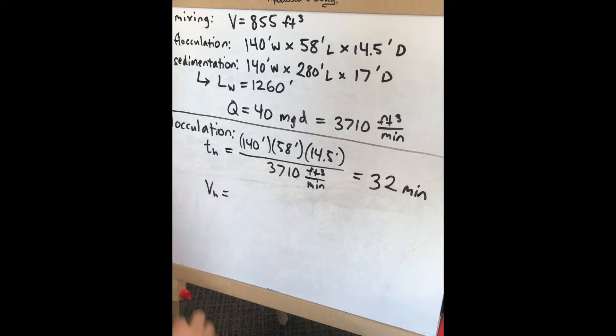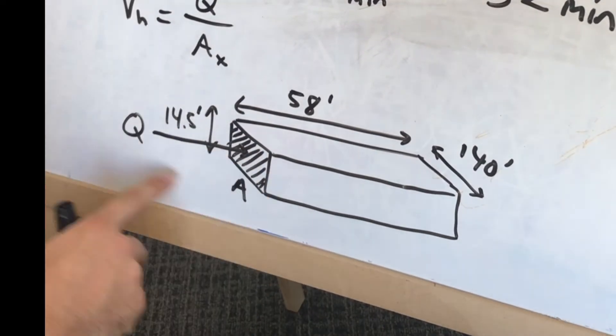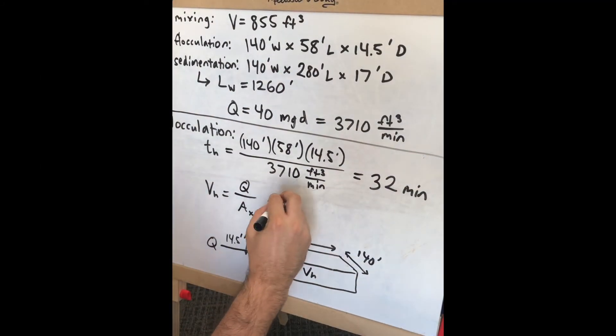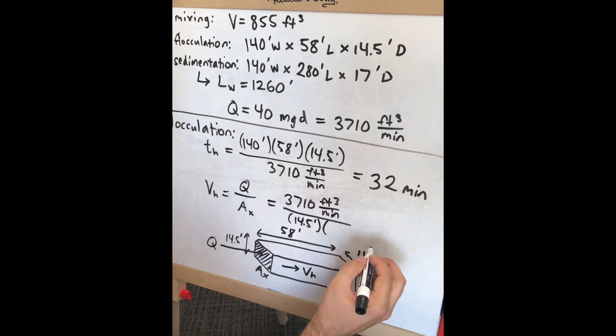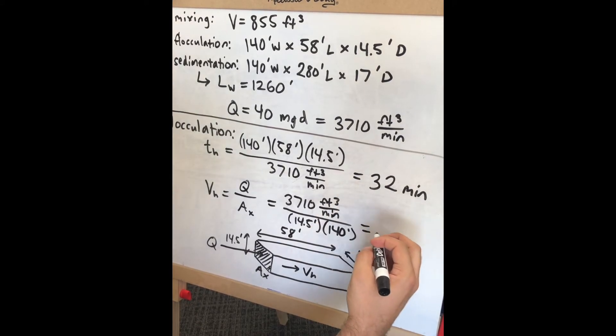For horizontal flow velocity, calculate the flow rate divided by the cross-sectional area. With a flocculation basin depth of 14.5 feet and width of 140 feet, we get 1.8 feet per minute.